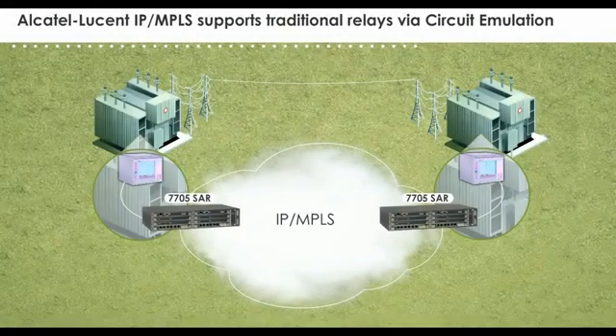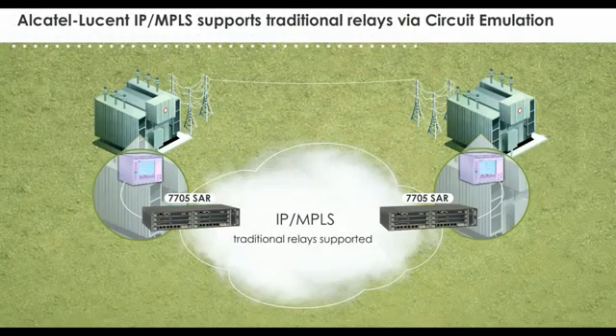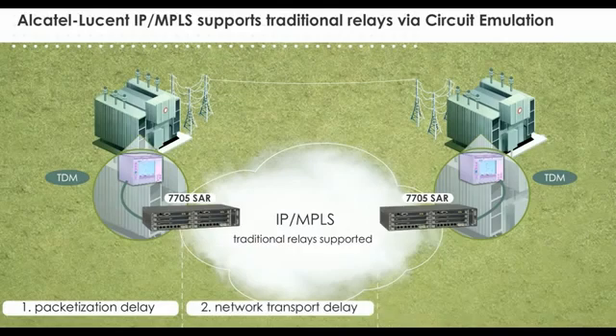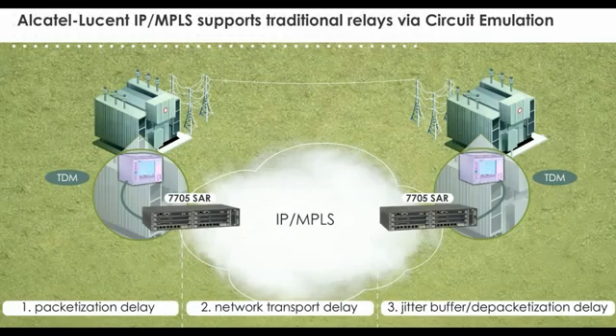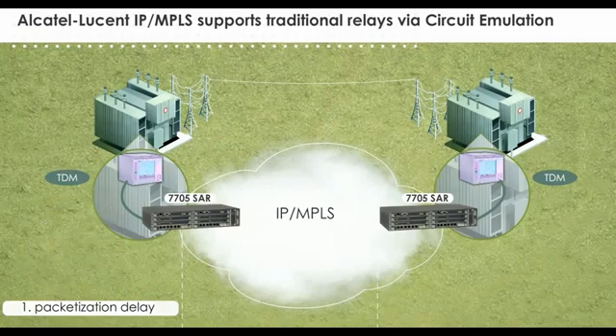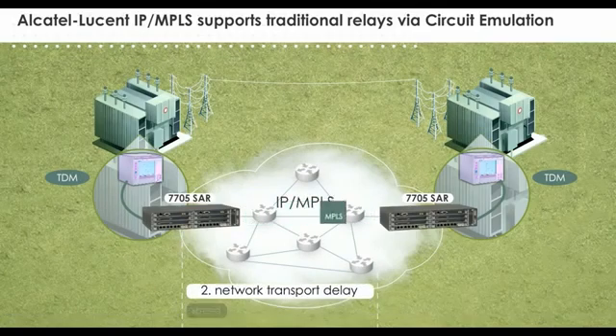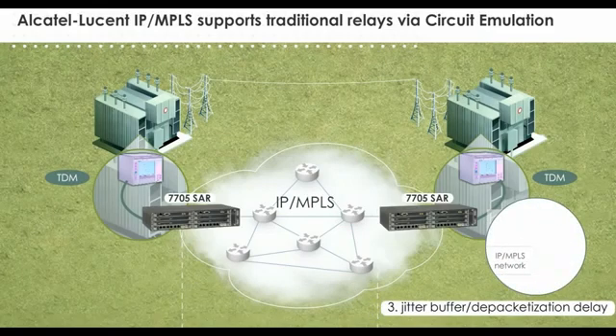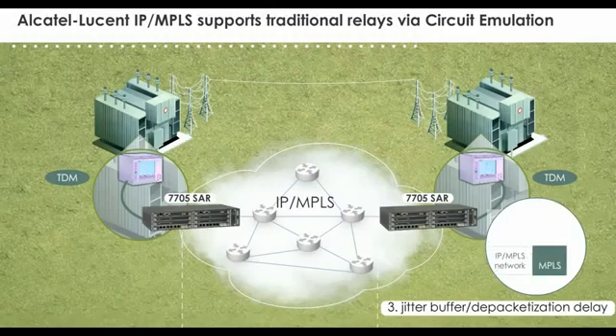The Alcatel-Lucent IP MPLS network supports traditional relays using circuit emulation service. For an IP MPLS network, the communication network latency for TDM traffic over IP MPLS consists of packetization delay, network transport delay, and jitter-buffer depacketization delay. Packetization delay relates to the process of transforming TDM traffic into packet data. Network delay relates to the fixed delay based on physical link speed and distances involved and a variable delay depending on the number of nodes traversed. Jitter-buffer and depacketization delay relates to the time required for a data packet to move out of the jitter-buffer and to get depacketized into a TDM stream connecting to the teleprotection relays.